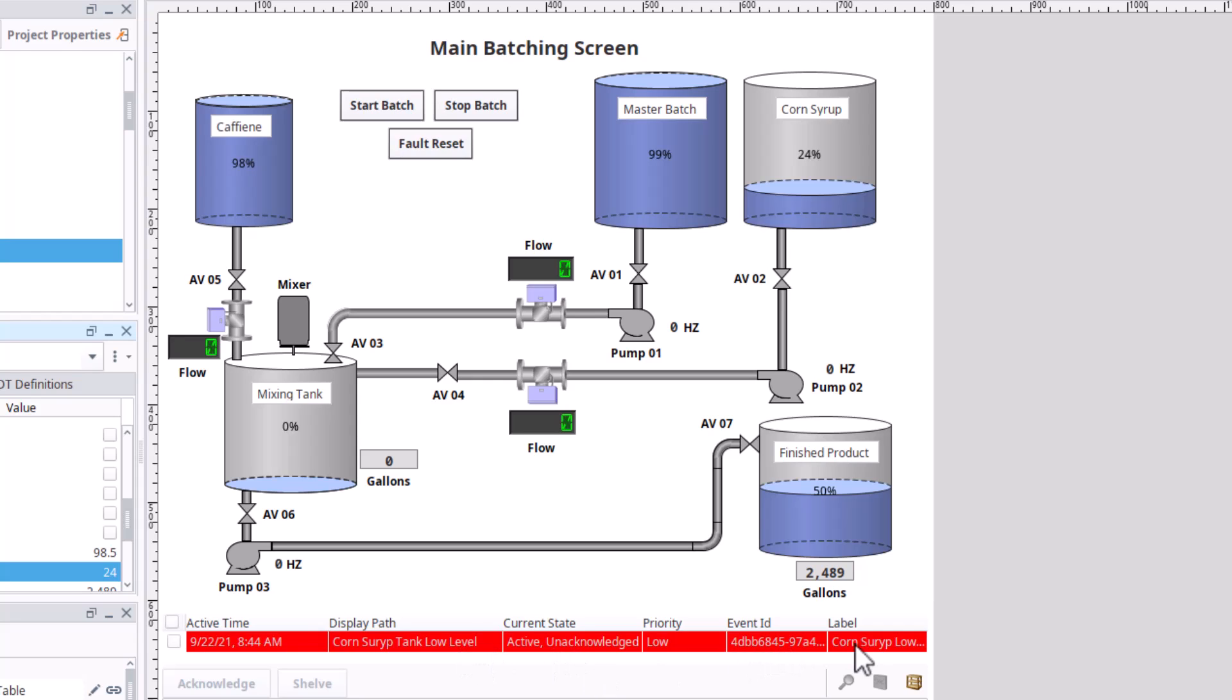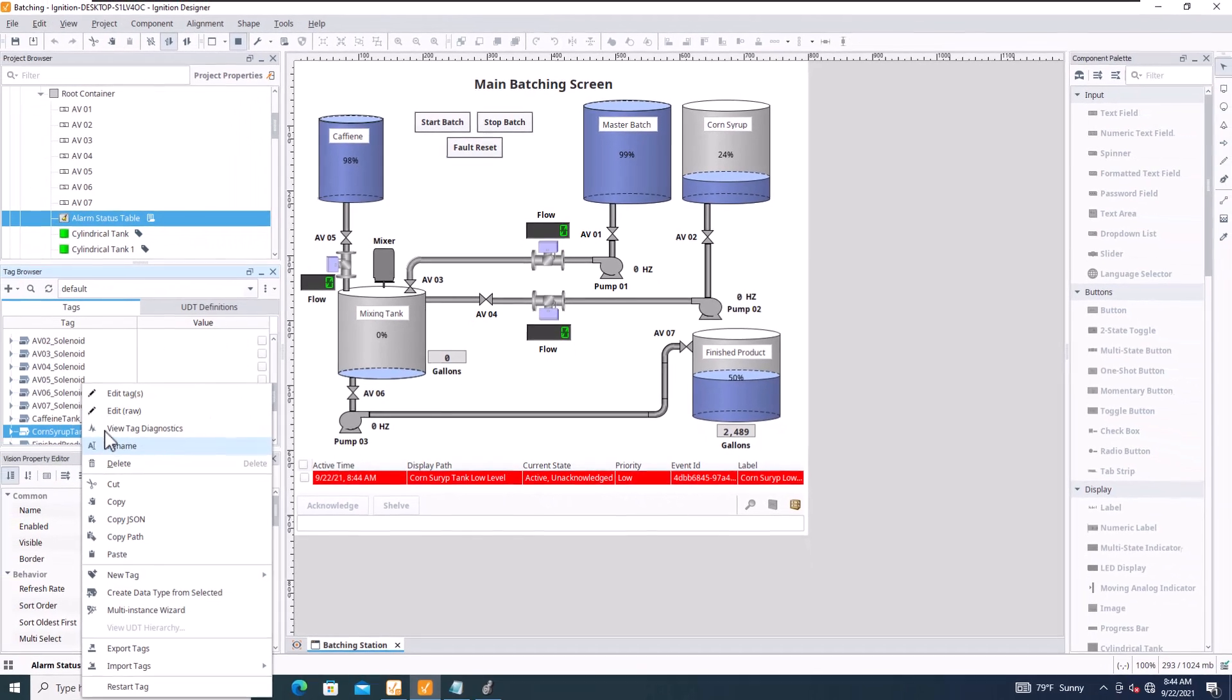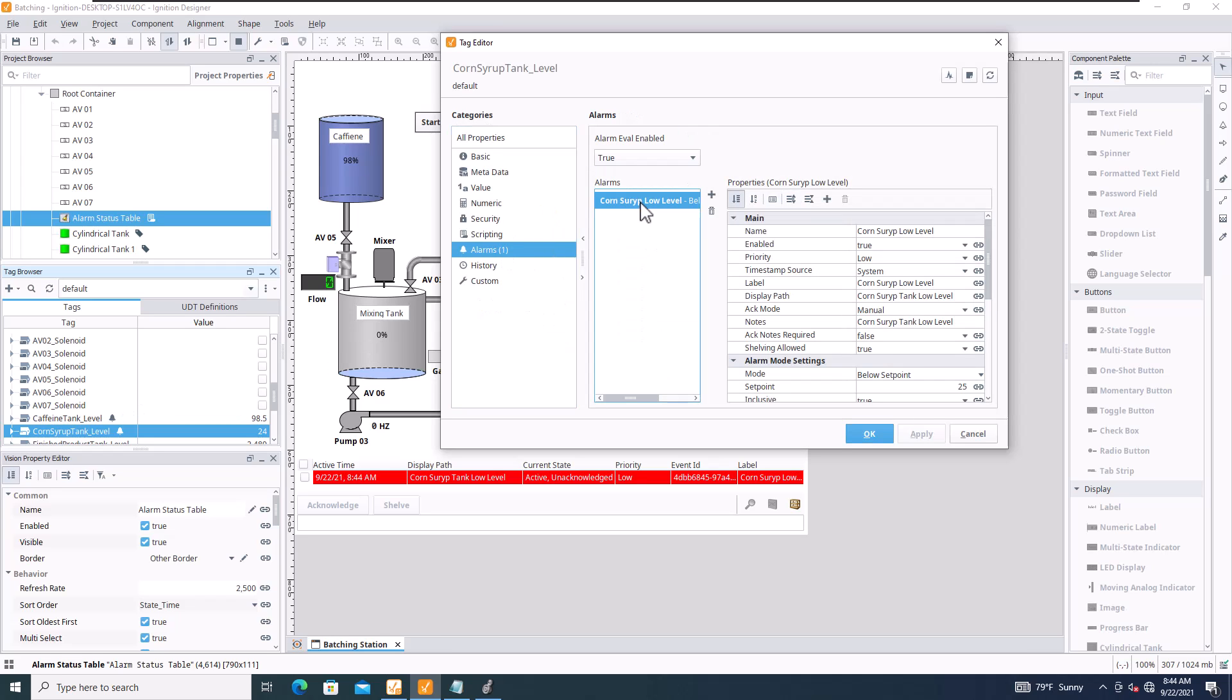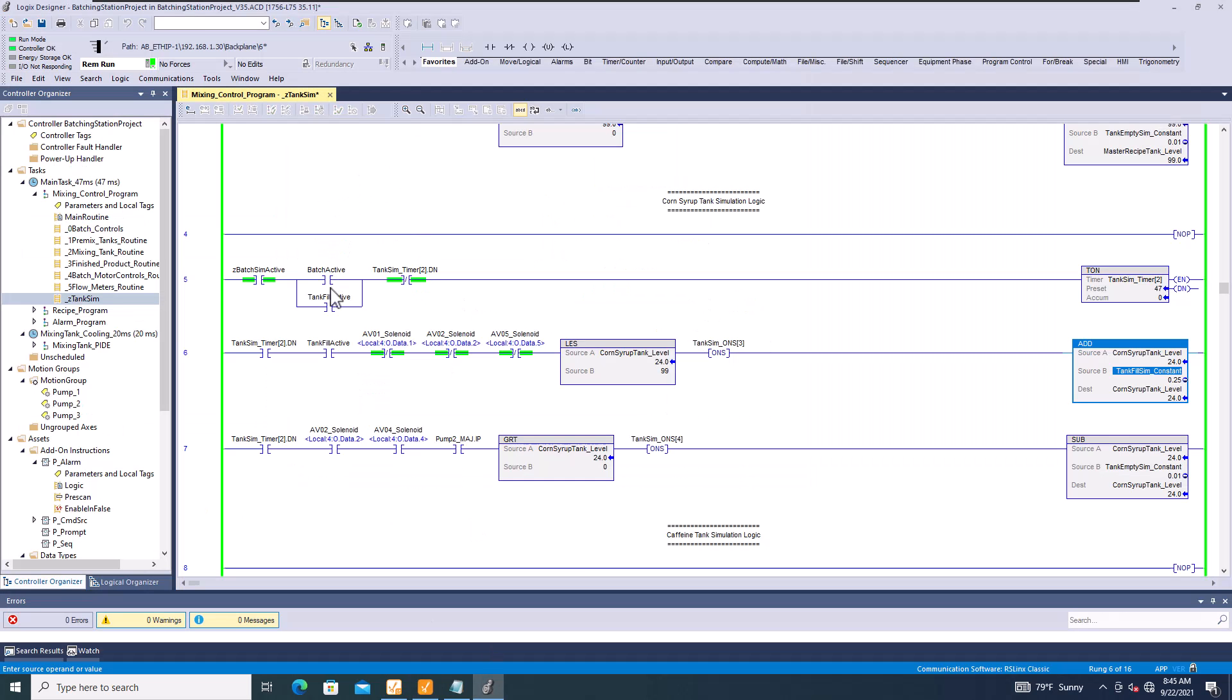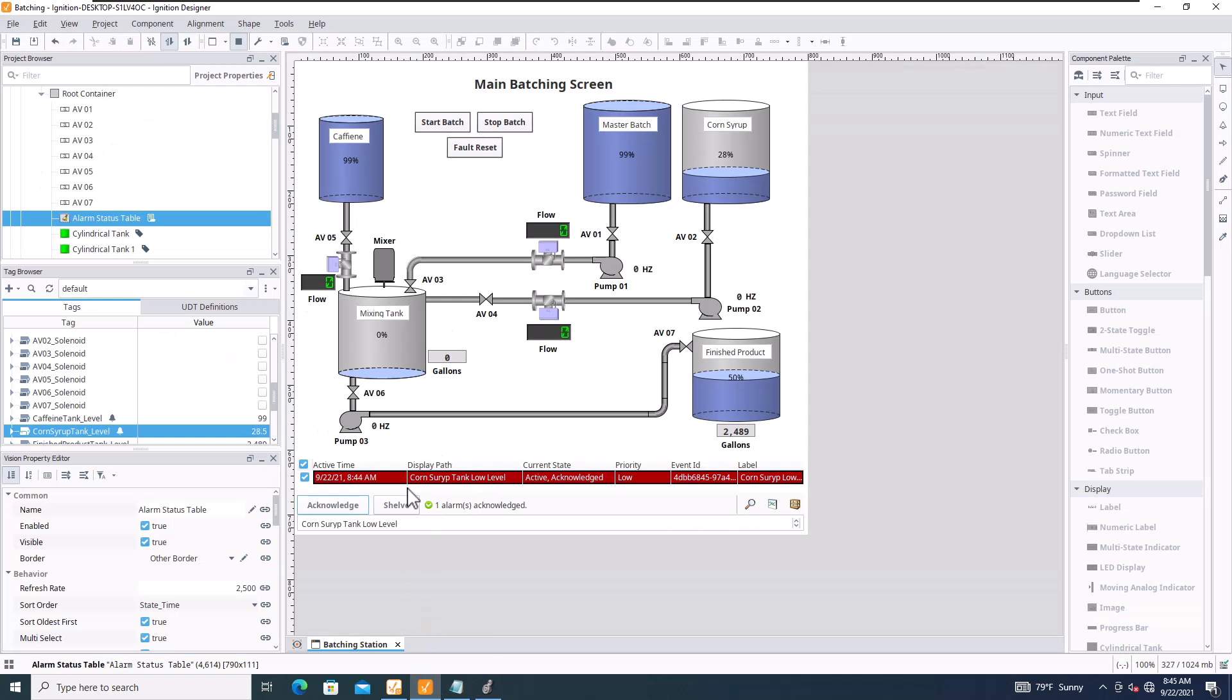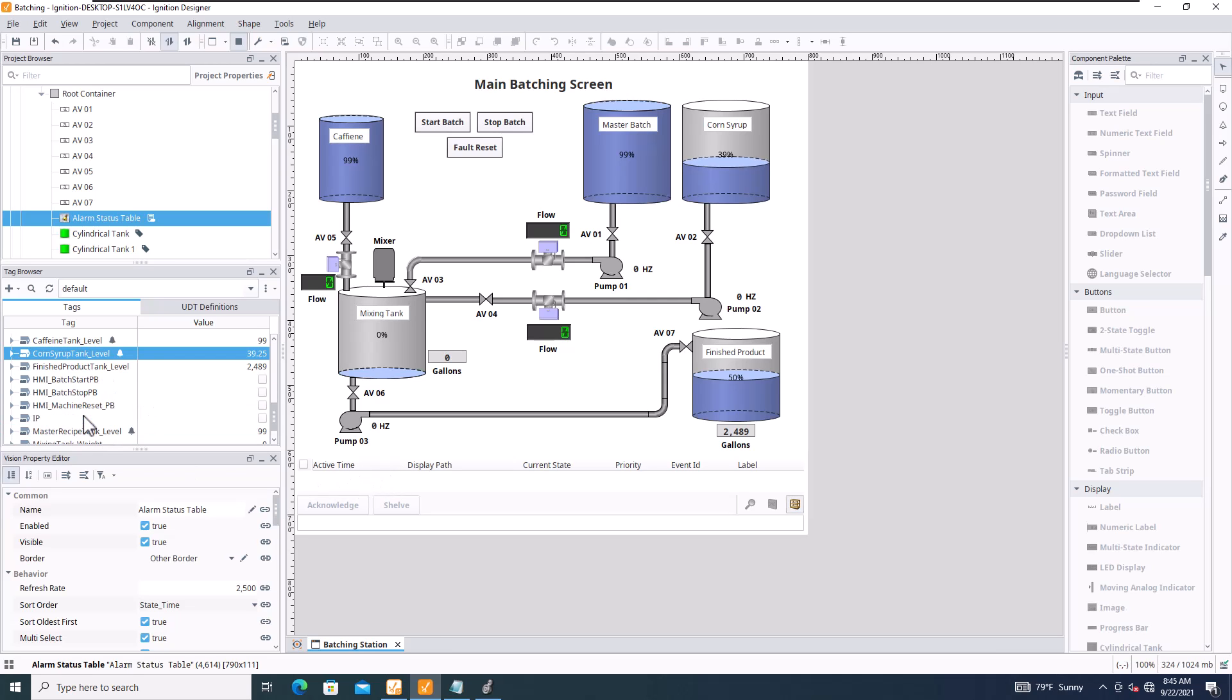And so over here it has a label, over here as the event ID, the priority. Again when it comes down to it you can change your priorities. It's very simple to change your priorities. You could change that to a critical or high priority if you want. And if we were to acknowledge that we can acknowledge it, but it's still going to be there because we haven't satisfied that it's above the actual point. As soon as it goes above then it goes back.